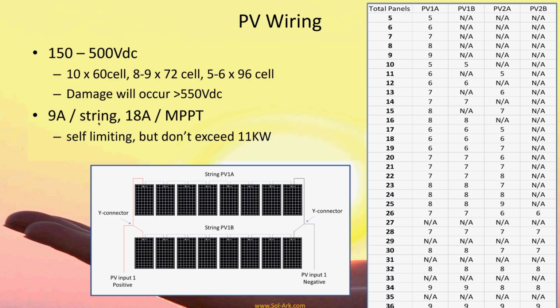We can do 9 amps per string, 18 amps per MPPT, and we really don't have to worry about it. It's self-limiting, so if we go a little over, it's not going to be a big deal, but please don't try and exceed 11 kilowatts because that is an issue.